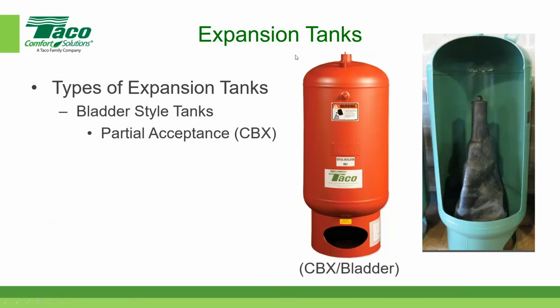Okay. The next category is called a partial acceptance tank, and just as the name implies, the bladder does not hold the same physical volume as the steel container. Again, in my cutaway version here, here's the steel container, and let's assume the steel container holds 200 gallons. You can see the bladder in this case is dramatically smaller than the one I showed you previously, and that bladder has less volume than the steel container. I'll show you with some examples later in this discussion, but for this picture, let's make an assumption and say that the bladder has a volume of 60 gallons. If the bladder volume is 60 gallons and the steel volume is 200 gallons, then we say it's partial acceptance. So partial acceptance means that the bladder has a smaller volume than the steel container.